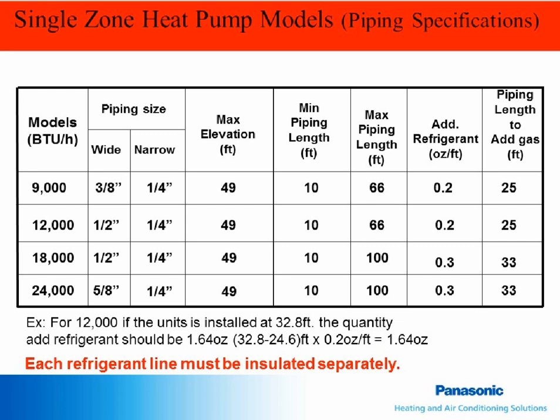The common question is, can I increase the diameter and length of the pipes beyond the factory recommendations? The short answer is no. Anytime you increase the lengths, you lose capacity, and you reduce oil flow or oil velocity if you increase the pipe diameters. In many cases, simply going up a half a ton in size will give you the extra length needed. Notice on this chart that going from a 12,000 to an 18,000 BTU unit will allow an additional 34 feet of line set distance, over 50% longer.